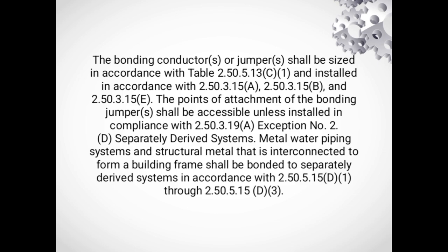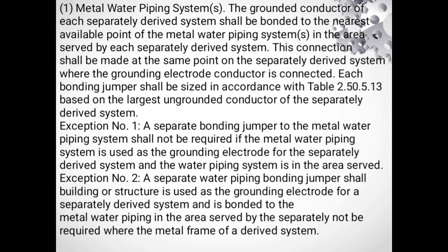Section 2.50.5.15 addresses the bonding of exposed structural metal. This is crucial for minimizing potential differences between structural elements and other grounding components. Number 1. Metal water piping system. The grounded conductor of each separately derived system shall be bonded to the nearest available point of the metal water piping system. In the area served by each separately derived system, this connection shall be made at the same point on the separately derived system where the grounding electrode conductor is connected. Each bonding jumper shall be sized in accordance with Table 2.50.5.13 based on the largest ungrounded conductor of the separately derived system.